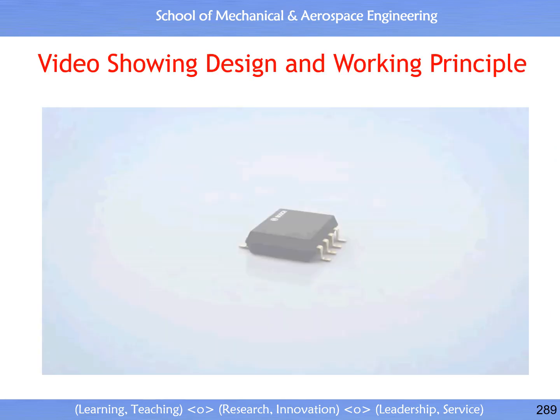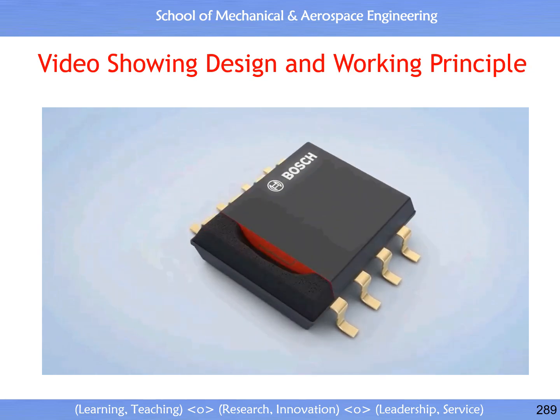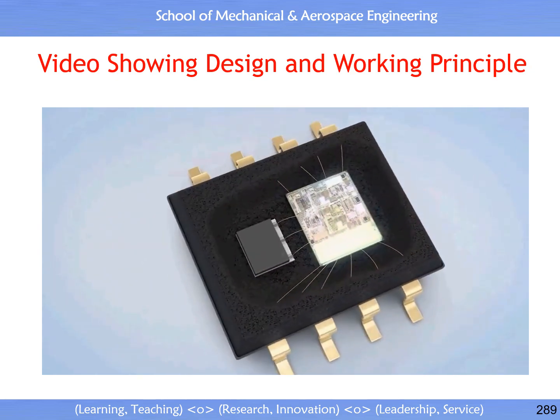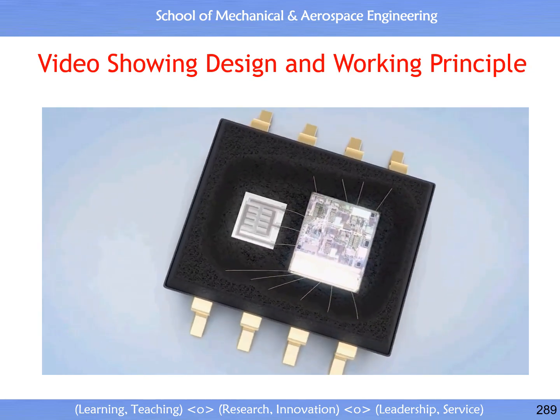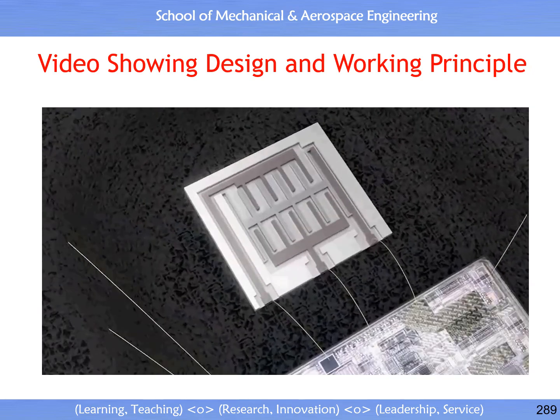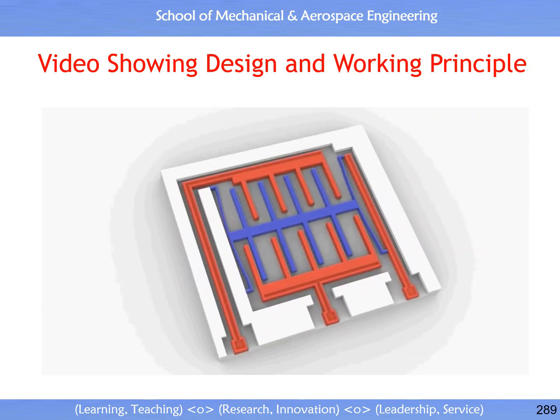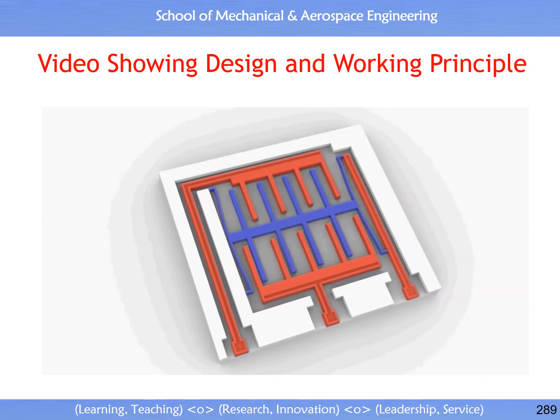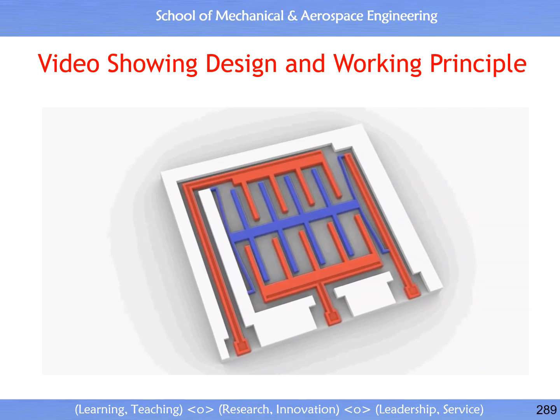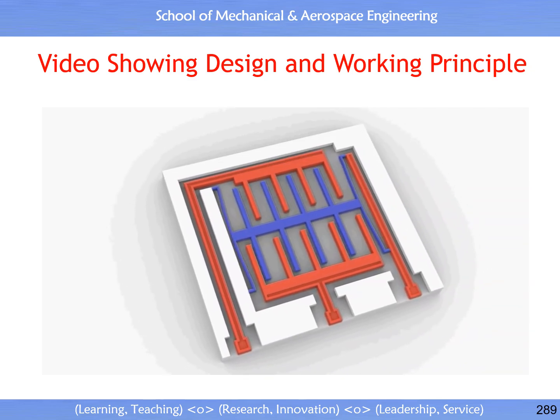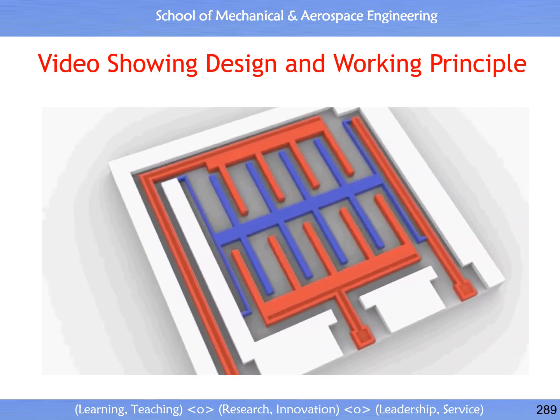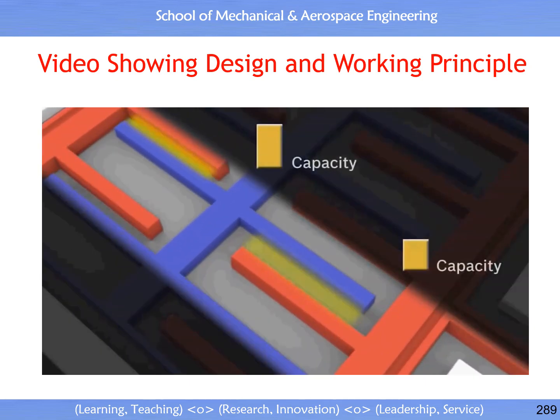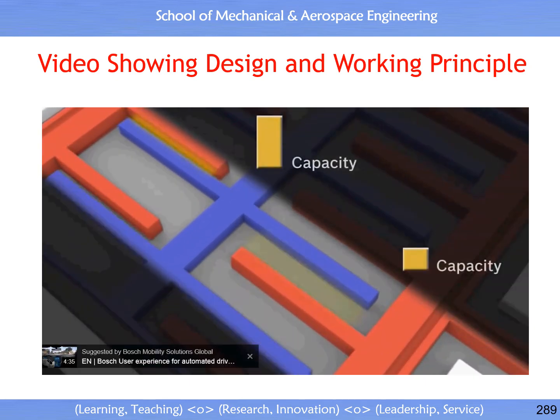The acceleration sensor combines two components in its housing, a signal processing chip and the actual micromechanical sensor. This comb-like structure is the characteristic feature of such a sensor. The blue part of this structure is movable. This part is deflected during acceleration and deceleration. The result is a change in the capacitance between the electrodes. This change is measured by the signal processing chip and converted into an output signal.